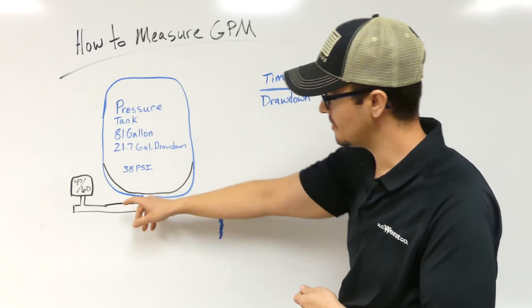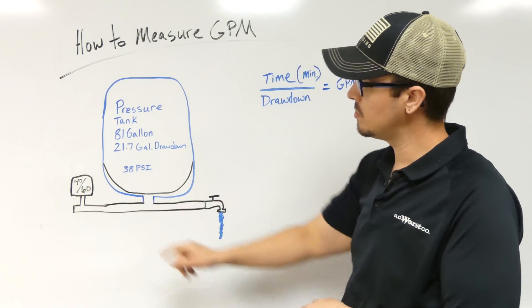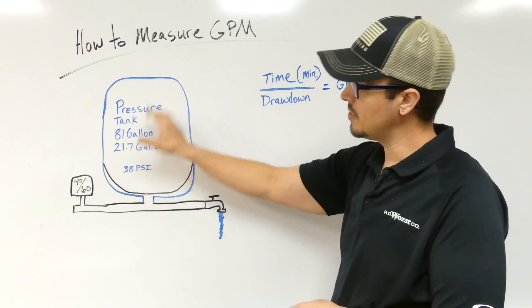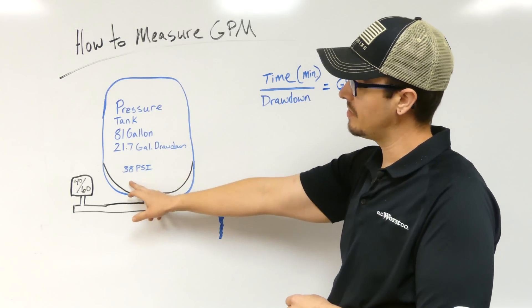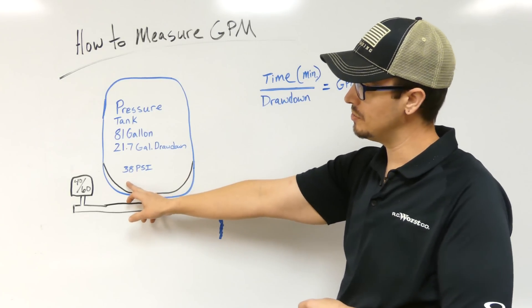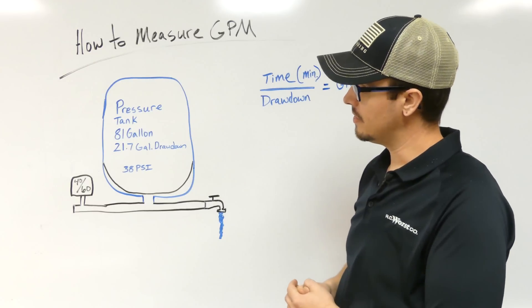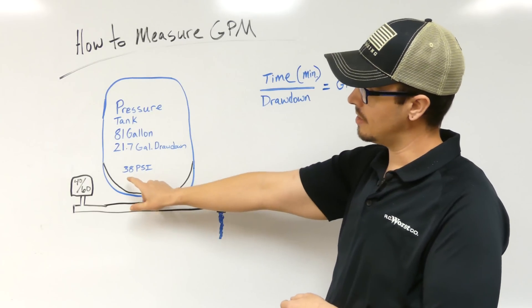It's a 40 to 60 setup, so we've got a 21.7 gallon drawdown. It's a good time when you're checking all this to go ahead and verify that your pressure tank is set to two to three pounds below your cut-in pressure on that pressure switch.